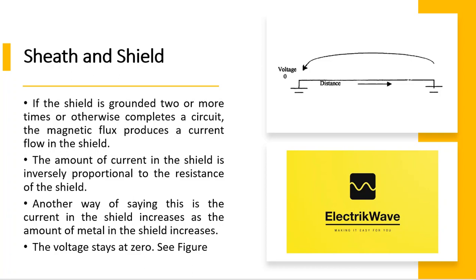If the shield is grounded two or more times, or otherwise completes a circuit, the magnetic flux produces a current flow in the shield. The amount of current in the shield is inversely proportional to the resistance of the shield. Another way of saying this is the current in the shield increases as the amount of metal in the shield increases, while the voltage stays at zero.